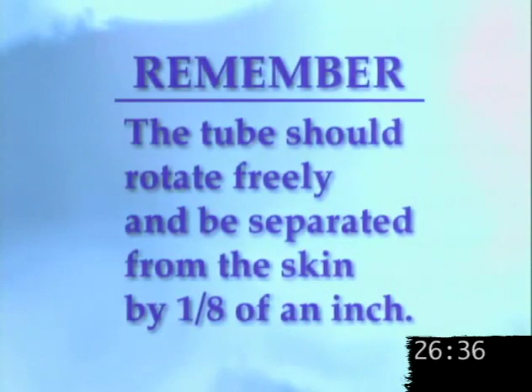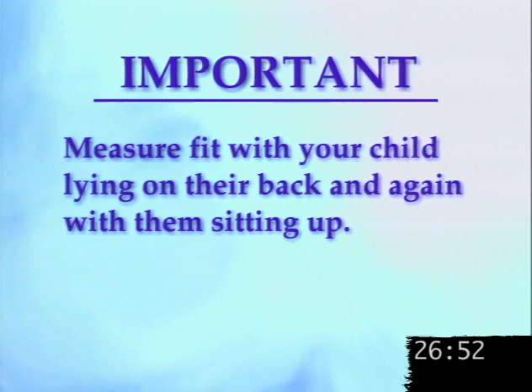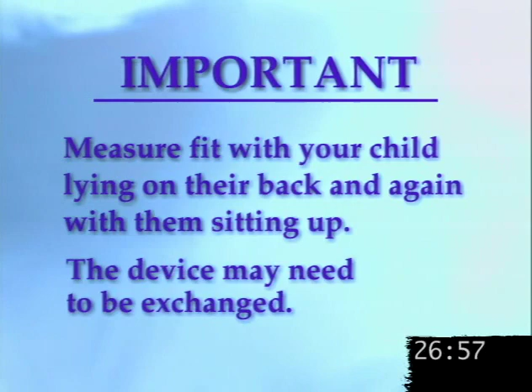Each device should rotate freely and have 1/8 of an inch of room above the skin. Good fit is important and should be checked frequently. Any device can cause a pressure sore if the shaft length is too short. For this reason, fit should be measured with the child lying on their back and then sitting up. Treatment involves exchanging the device for the appropriate size.